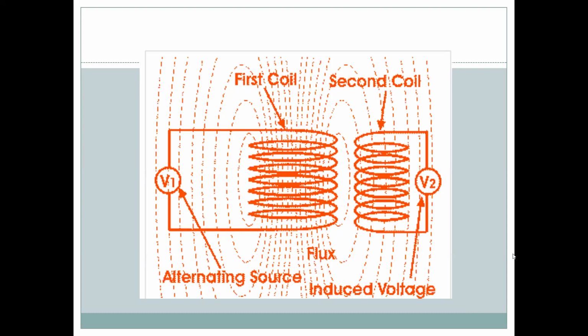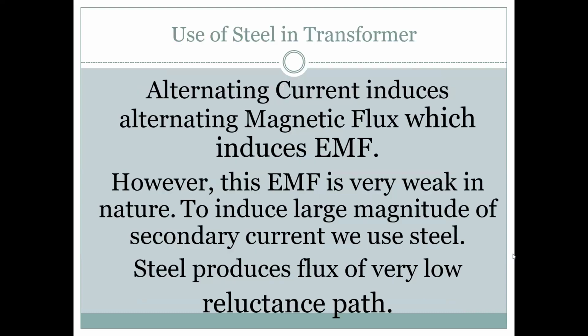So if we see the next slide, next. Alternating current induces magnetic flux, which induces an EMF, electromotive force. However, this EMF is very weak in nature. To induce a large magnitude of secondary current, we need steel. It is a very, very special steel. It is not the standard steel that we manufacture, commercial steel. Steel provides a very low reluctance path for flux. Like a very low resistance path for electrical current, similarly, flux goes to the low reluctance path, that is, to the steel.